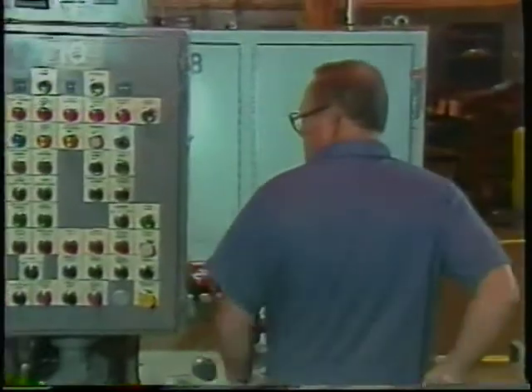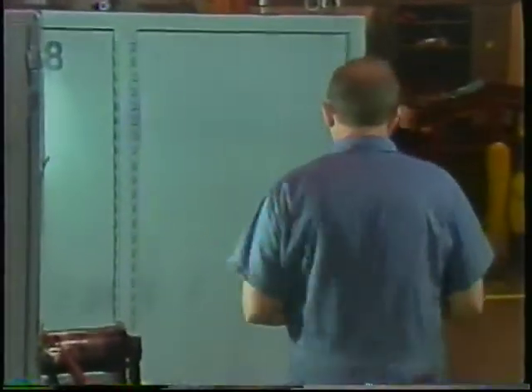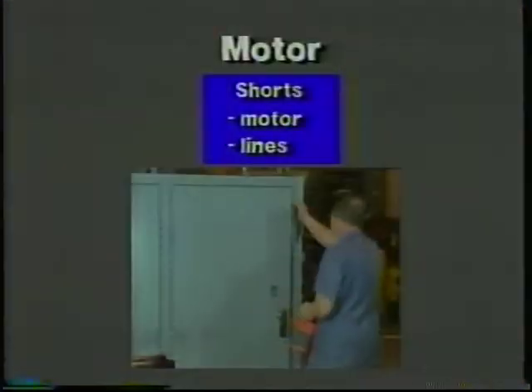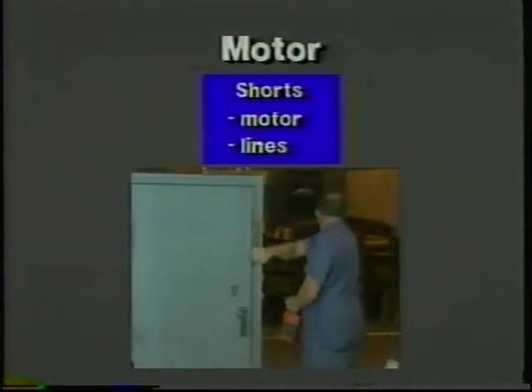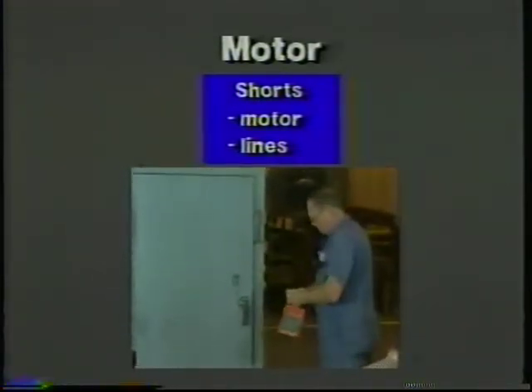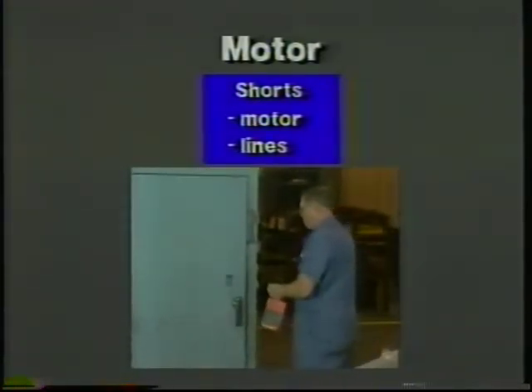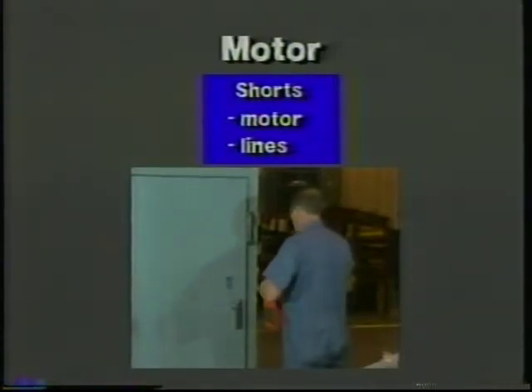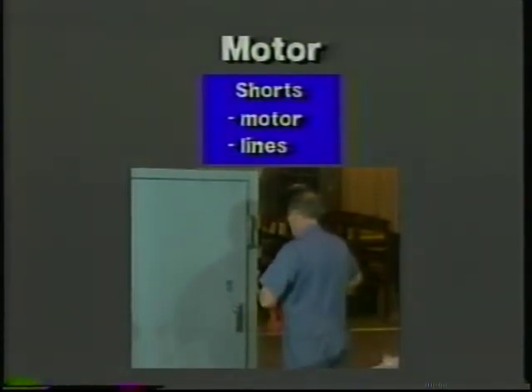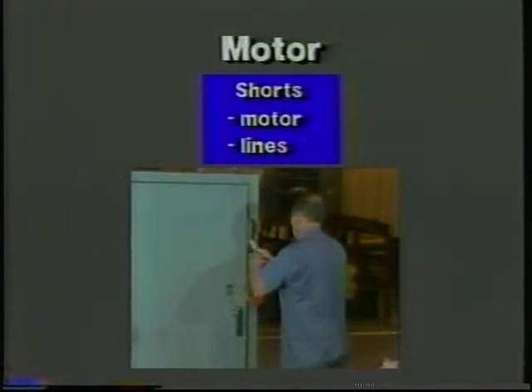Now try to start the motor. The fuse will blow or the breaker will trip immediately. This tells you that the short is very likely in the motor or in the lines to it on the motor side of the contactor. Lock the system out and take resistance readings at the motor junction box to isolate the short.